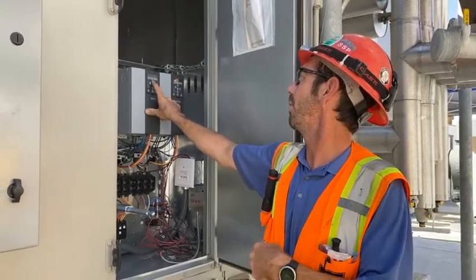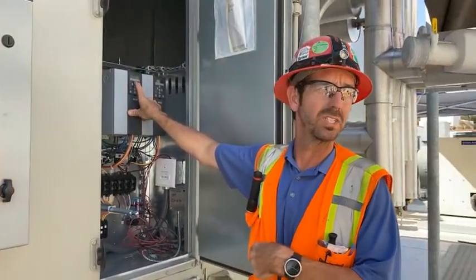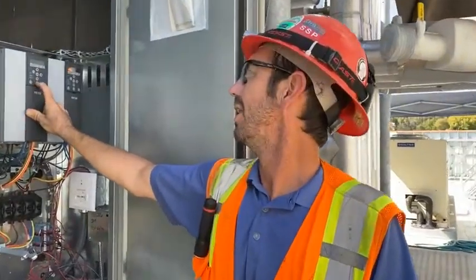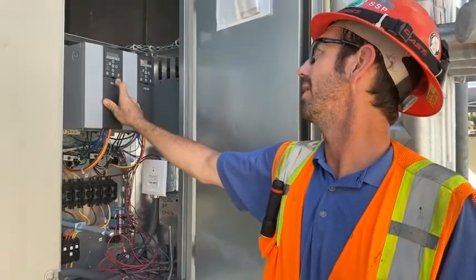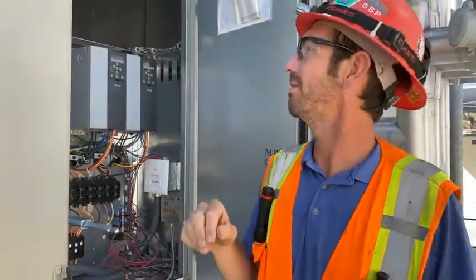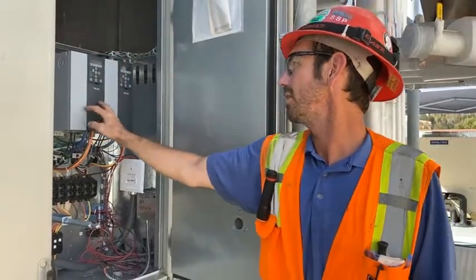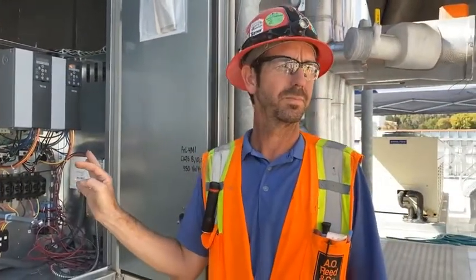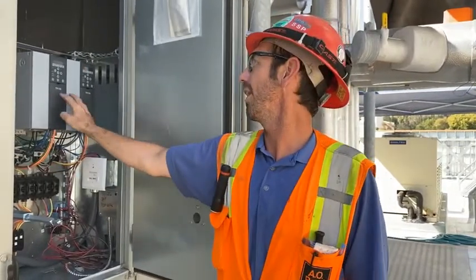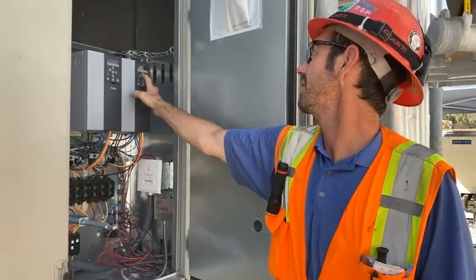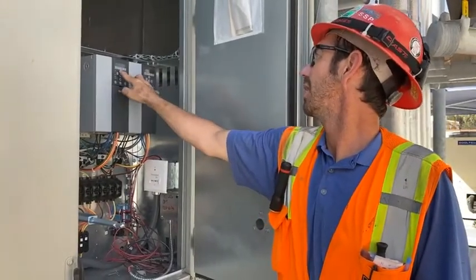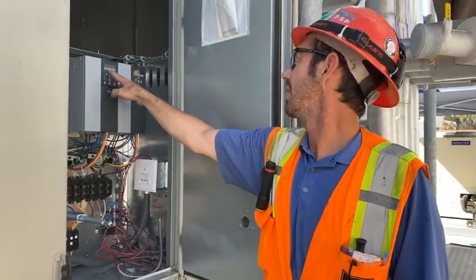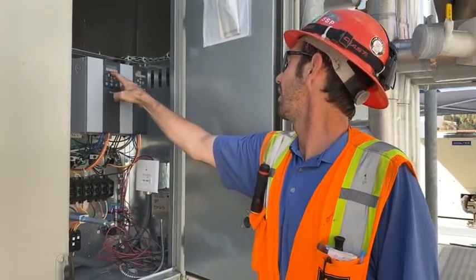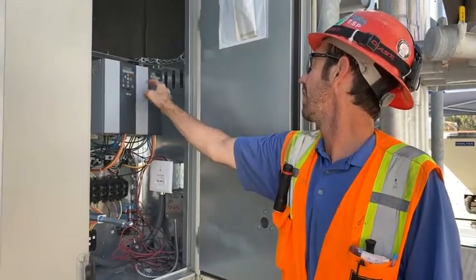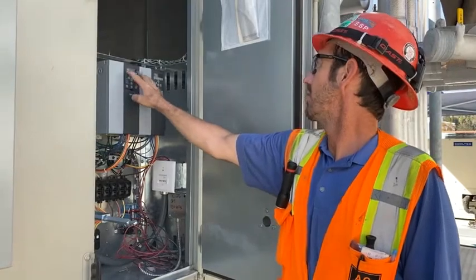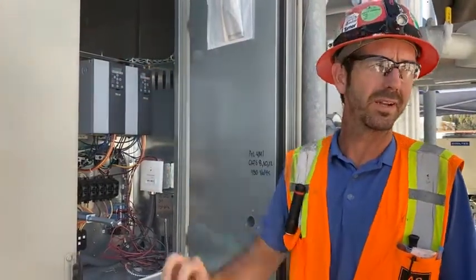You can move the arrow over one more and go up by single digits, 21, 22, 23 as I press the up arrow, okay? Again, we want to make sure we're in auto mode. In auto mode, if we don't have a signal, it's trying to turn back off. You guys have any questions on the VFDs or any of the controls inside this unit? You get what it does? We want both in auto. We want both of the speed signals to match. So they're both on hertz and horsepower. That way you can compare the numbers together, okay?